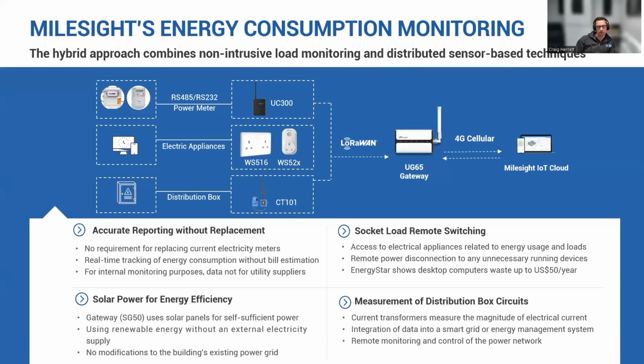The other side of the EMS solution is they're also using it to monitor and see where savings can be made. For instance, Unit 1 might have a CT101 running a lighting circuit. We understand that circuit has a minimum current that needs to run through it, but the CT101 may show this lighting circuit was running at a time of day when we know there'll be light coming through, so actually it's a waste of energy using those lights.